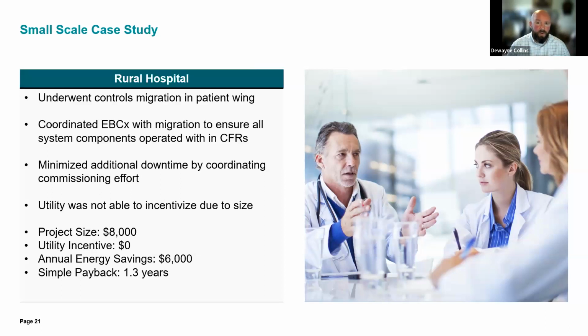So they wanted to coordinate some commissioning to make sure everything in that control loop worked per how they needed to operate that patient wing today, those CFRs. By doing this, they were already going to have a migration in which they had to schedule some downtime in those areas. We were able to maximize that time by commissioning it at the same time, thereby eliminating extra downtime for that commissioning effort.